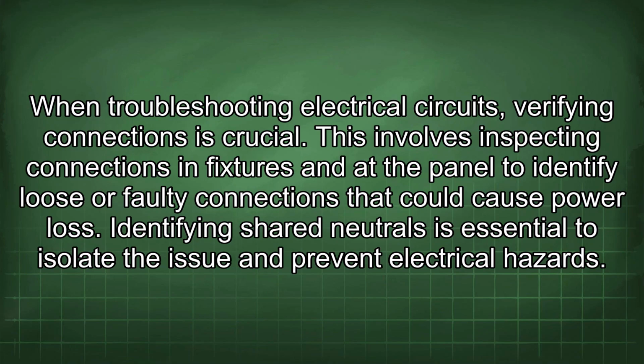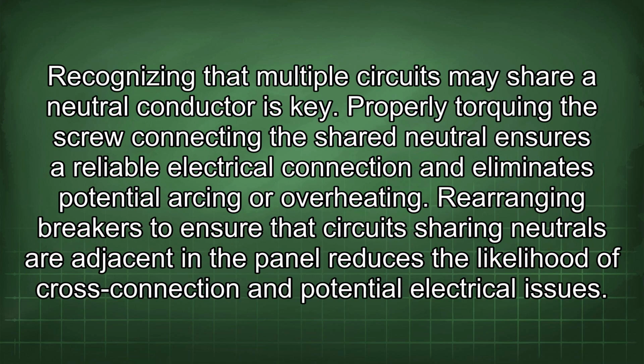When troubleshooting electrical circuits, verifying connections is crucial. This involves inspecting connections in fixtures and at the panel to identify loose or faulty connections that could cause power loss. Identifying shared neutrals is essential to isolate the issue and prevent electrical hazards. Recognizing that multiple circuits may share a neutral conductor is key.